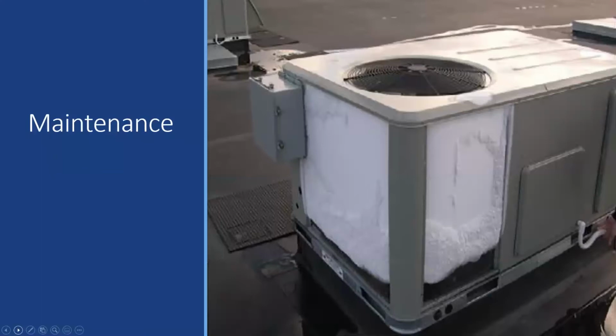Maintenance. Lack of maintenance or the deferment of maintenance on your equipment will have an impact on its performance. You want to check at the start of the season and at the end of the season to put things back how you found them. In this picture, this is an AC and an HVAC unit. The panels have been removed so that you can see the coils. In this case, the coils are frozen.